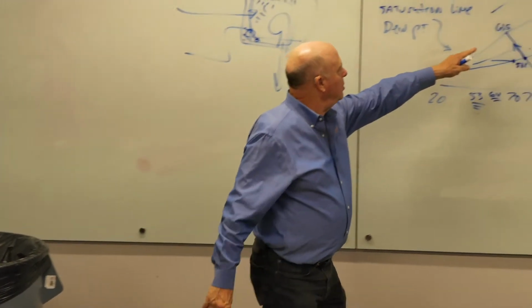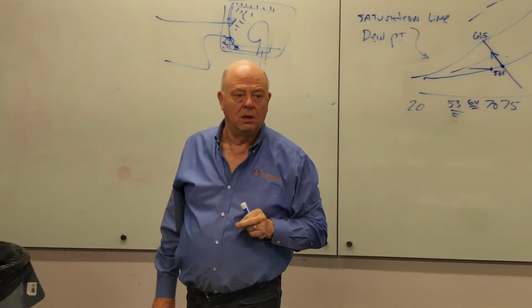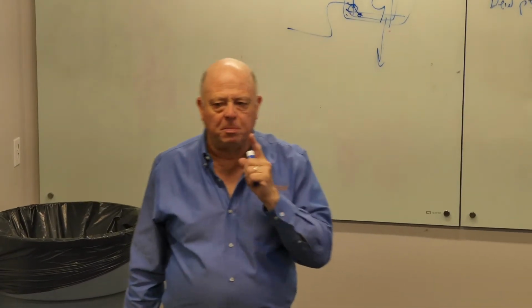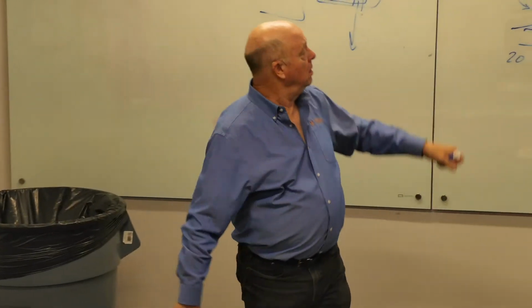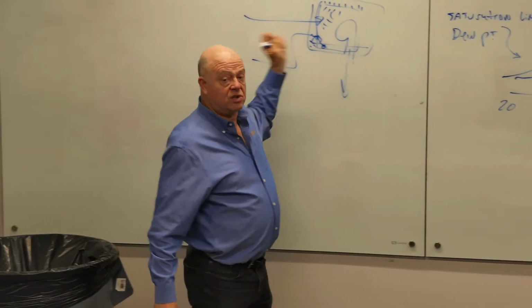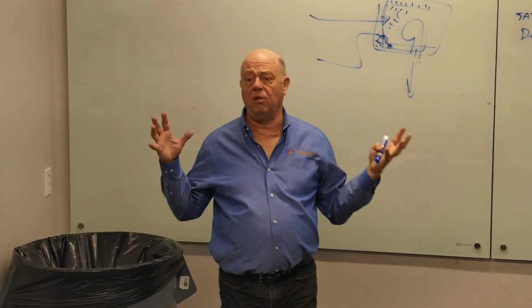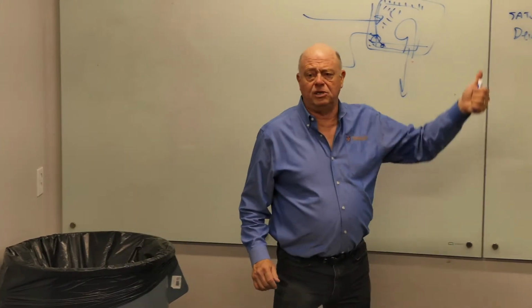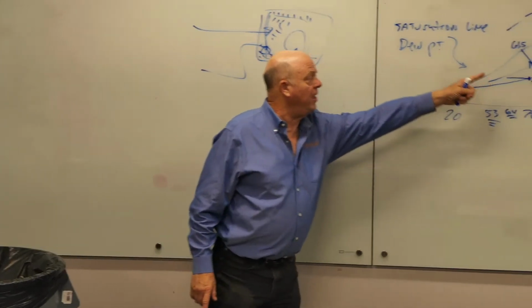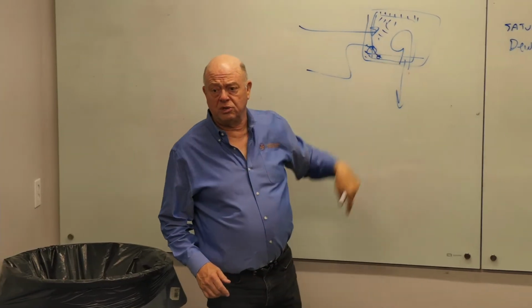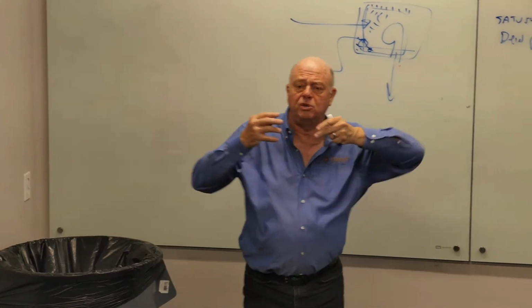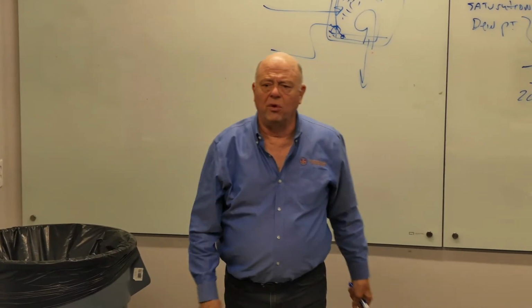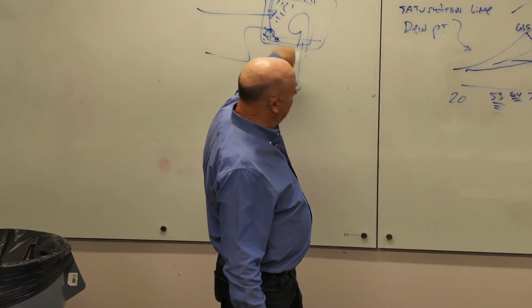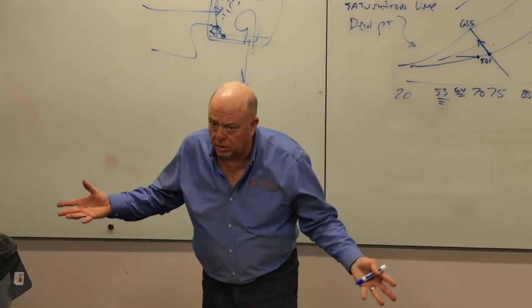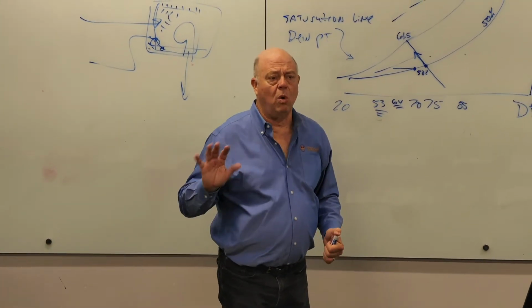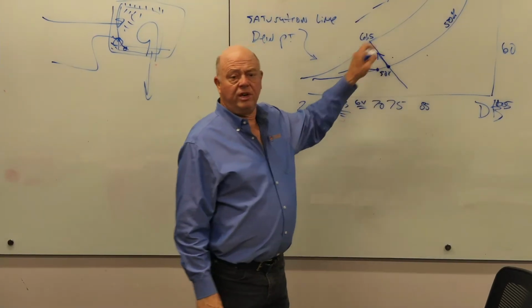Do you think that with a swamp cooler we'd get all the way to full saturation? If it's brand new, like, there's some variables. For one thing, how much air are we putting through here? What's the velocity through here? If we're screaming all the air it can do, we don't manage to evaporate as much, or, you know, get as far up that temperature line as if we were running this really slow. Because if we're running it really slow, there's more exposure to the water, and it gets a little further up there. So the velocity, the total CFM we're delivering is a variable here. But typically, a swamp cooler will do somewhere between 70 and 80% efficiency.